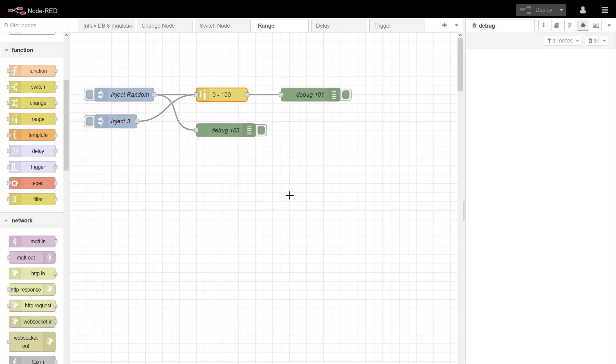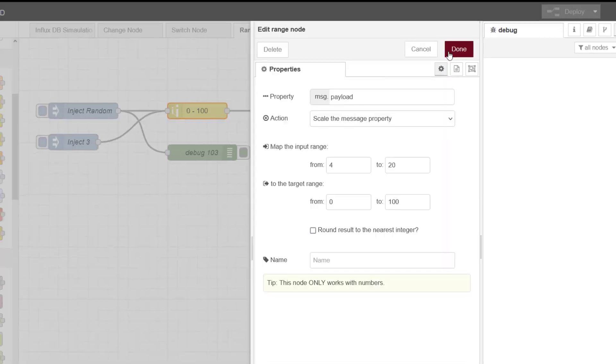An example where we might want to do this: in the process industry we use milliamp signals for a lot of our sensors, and those will be ranged from 4mA to 20mA for very good reasons. For some applications you might have a value that goes down just below 4 because your cable resistances aren't quite right, but having a negative value appear on your SCADA or your DCS could throw out all sorts of alarms, so you can scale your value to ignore that.